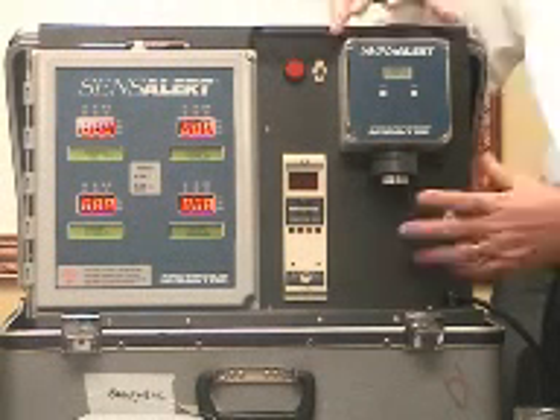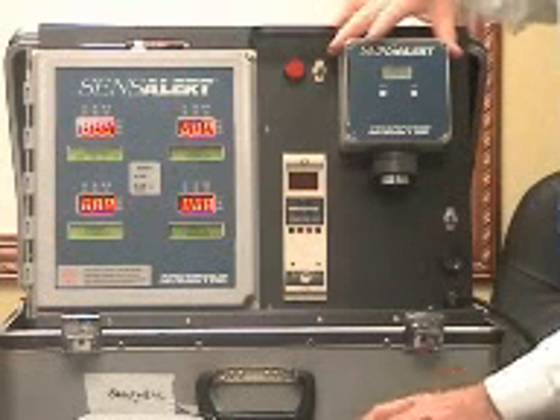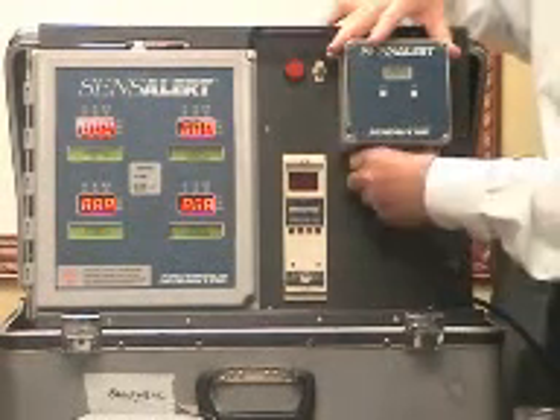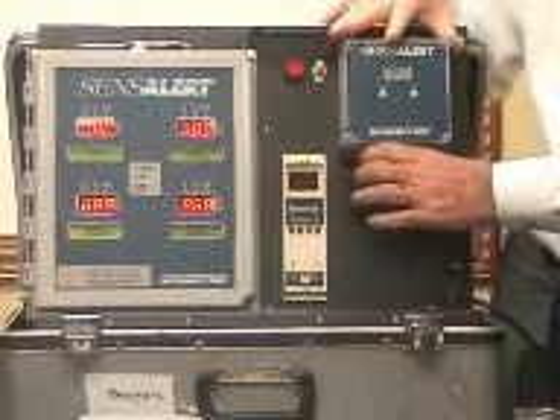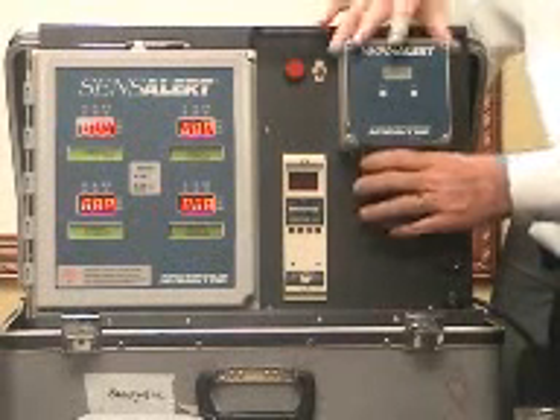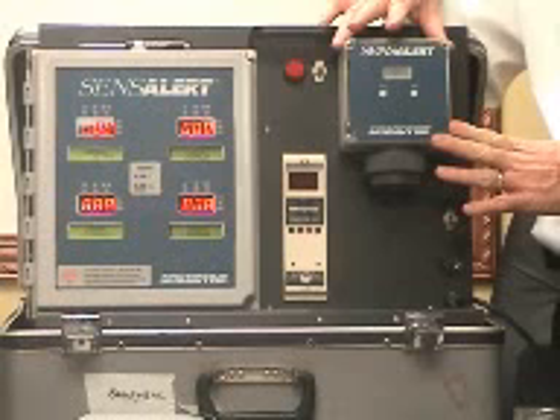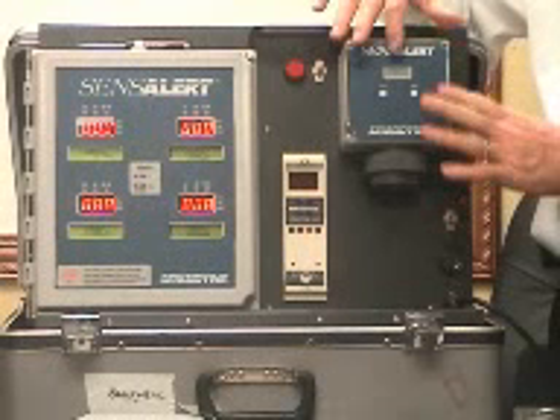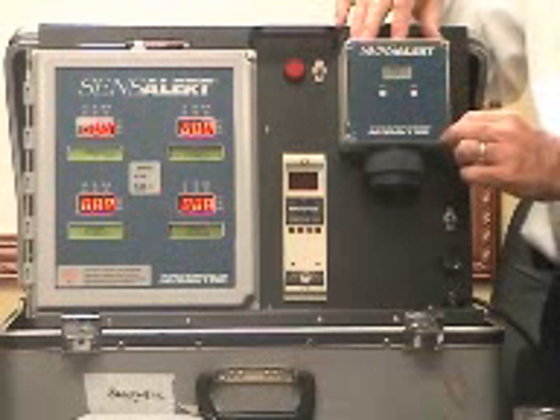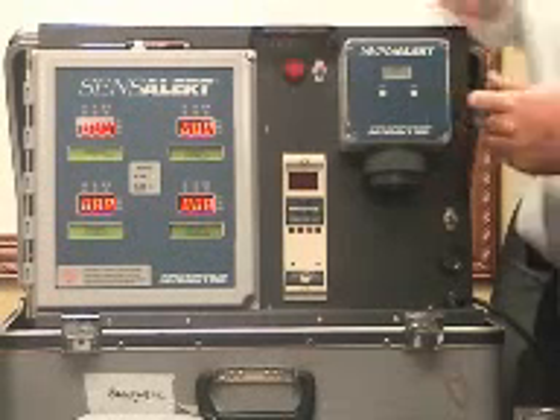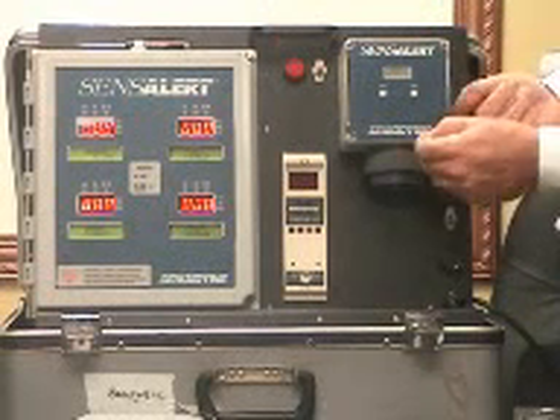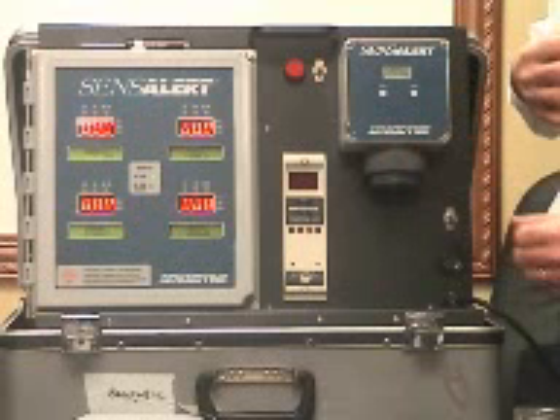But this is a good demonstration of how the transmitter is universal, where a customer can have several different gases in his facility and buy one transmitter and standardize on it. And a low-cost, very functional, easy to calibrate transmitter. There's no calibration tools, no meters or voltmeters needed to adjust the calibration or to zero it.